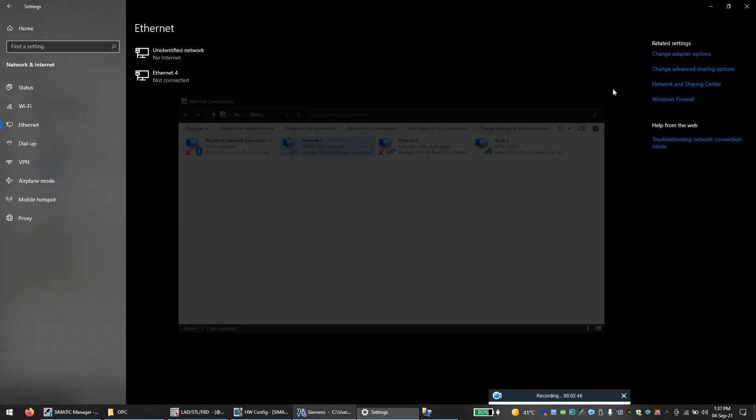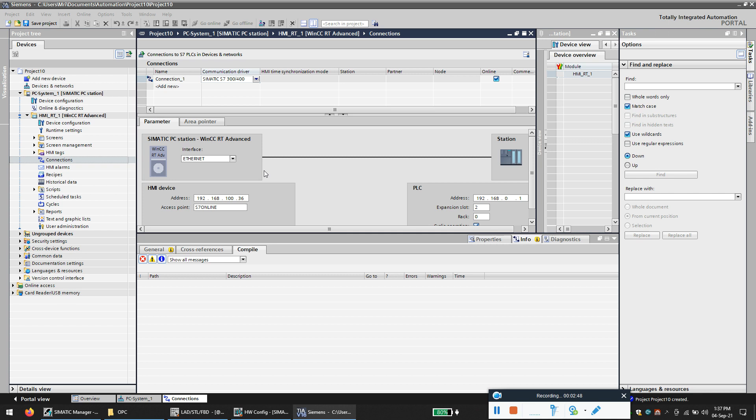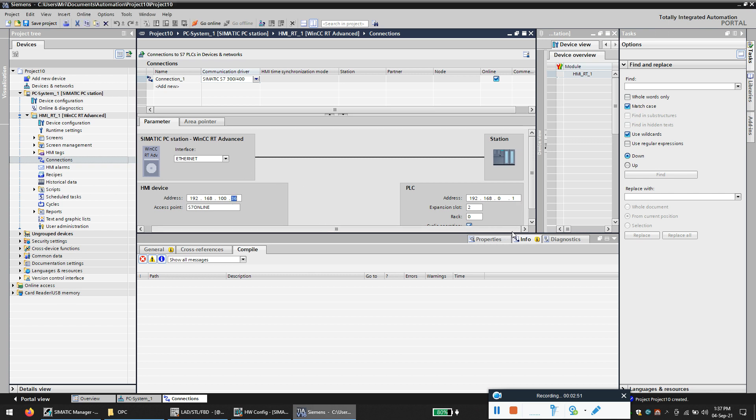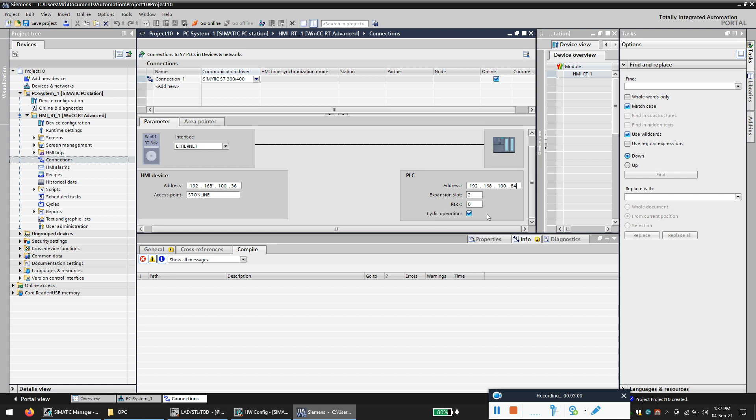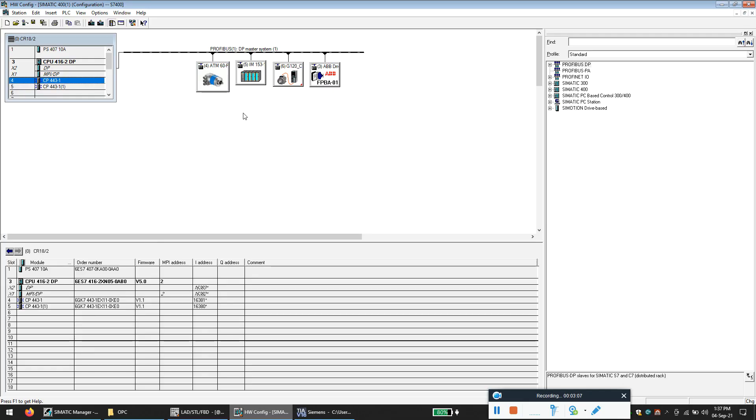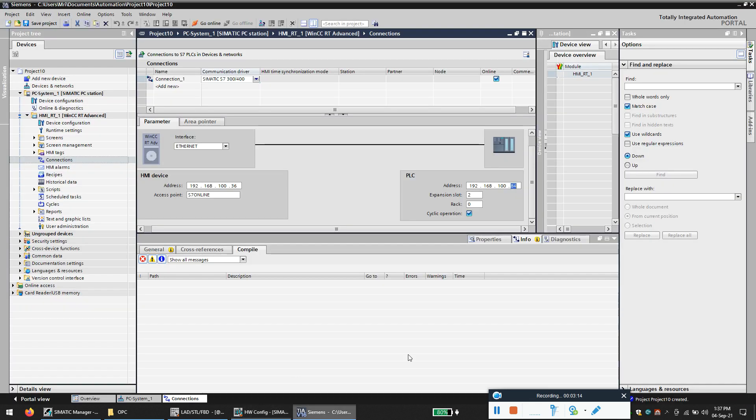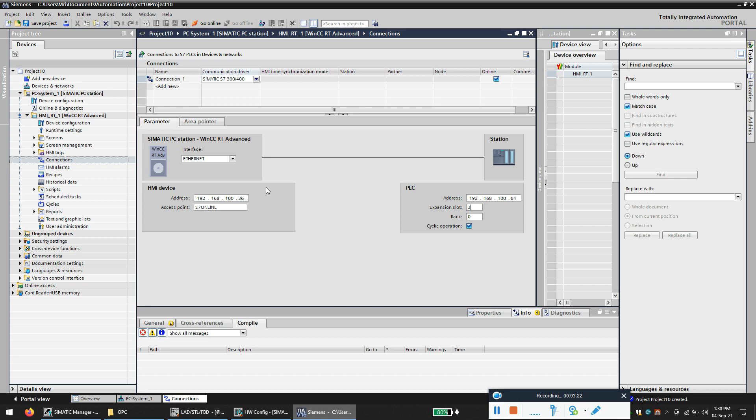It's 36, then put your PLC address that is 192.168.0.85. And you should mention this slot and rack number correctly by checking the hardware. So as you can see my rack number is zero and my PLC slot number is at three. So here the slot number is three. So that's it, my connection is made from WinCC SCADA to the PLC.